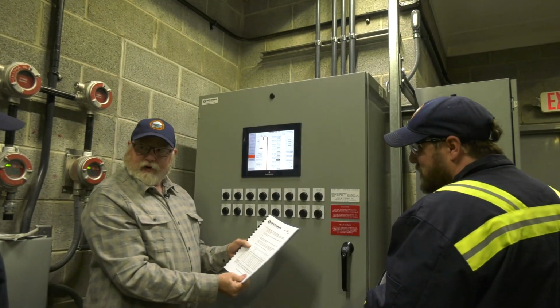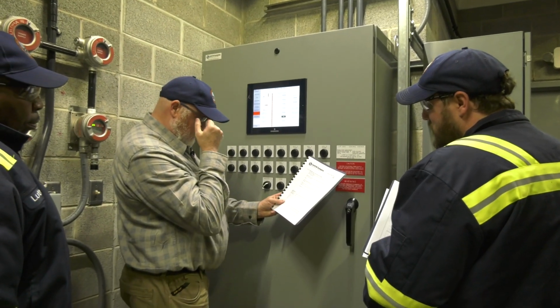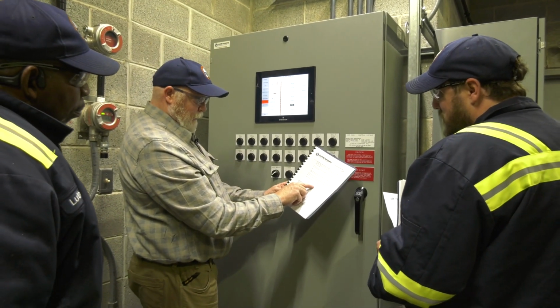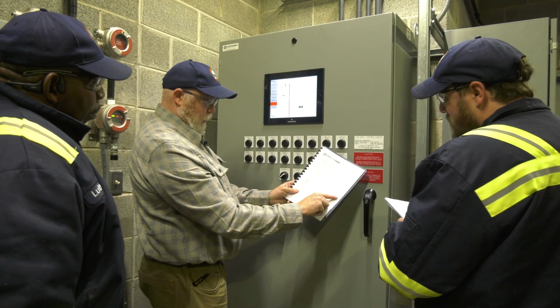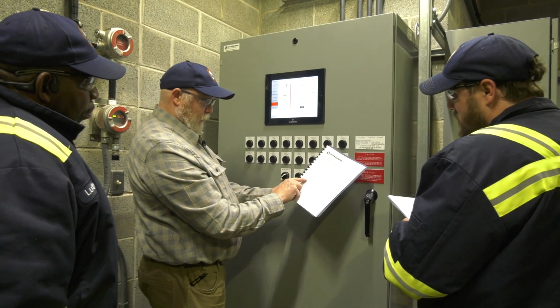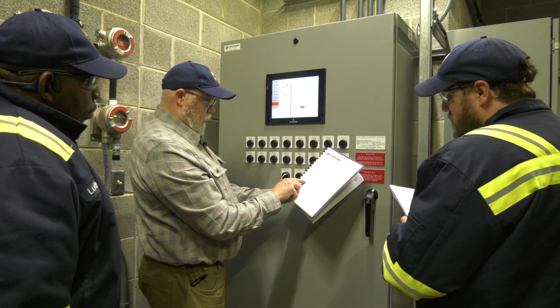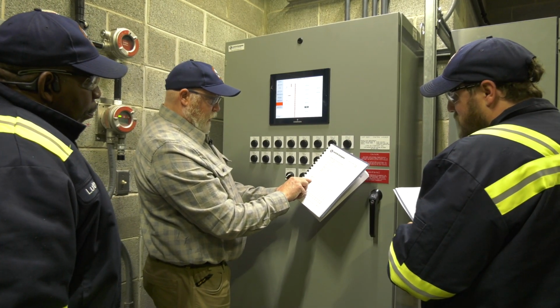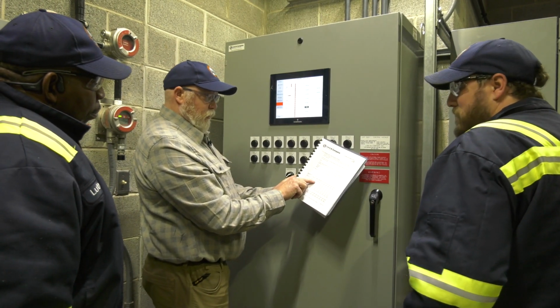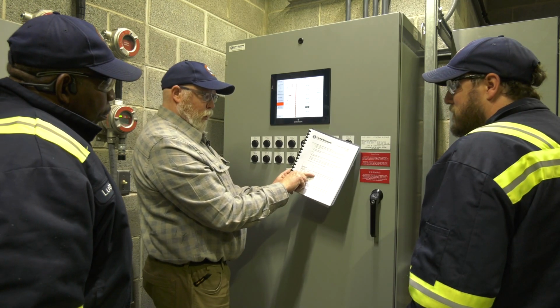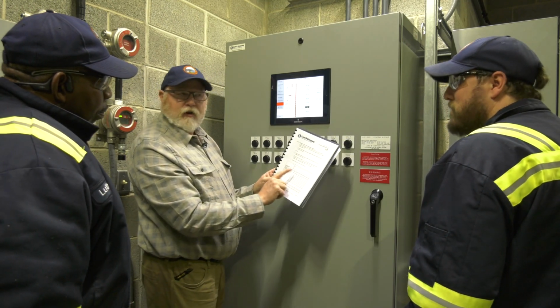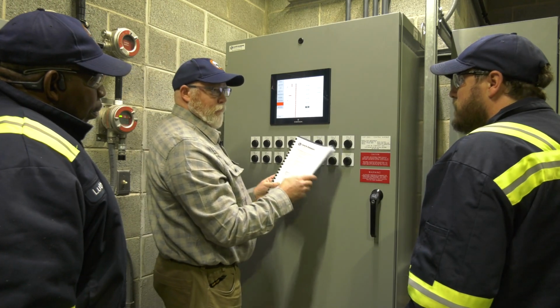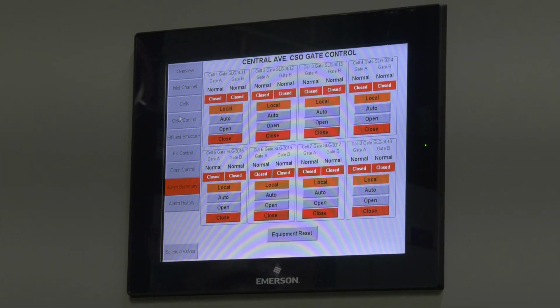This is a pretty handy table to have. Each piece of equipment, you go down here and it tells you if the LIT is greater than set point, then it goes through and tells you which gates or valves should be open or closed in automatic. So this table here explains the whole document. All right.